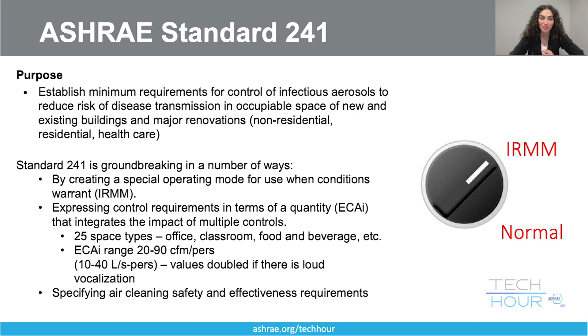Now, ASHRAE Standard 241 is groundbreaking in many different ways. One of them is establishing an infection risk mitigation mode. Another is equivalent clean airflow, which integrates ventilation, filtration, and air cleaning into a single performance requirement. It has 25 space types, and the equivalent clean airflow ranges from 20 to 90 CFM per person. And that's not only outdoor air; it could be outdoor air ventilation and filtration. Also, it includes safety and performance requirements for air cleaning technologies.